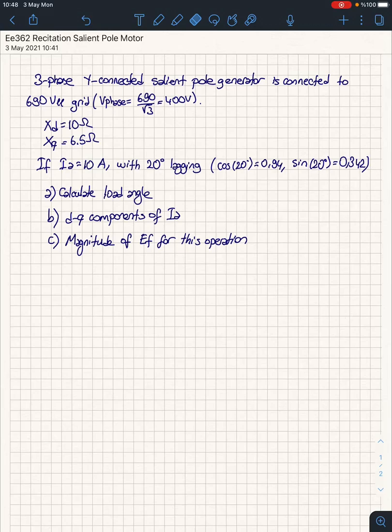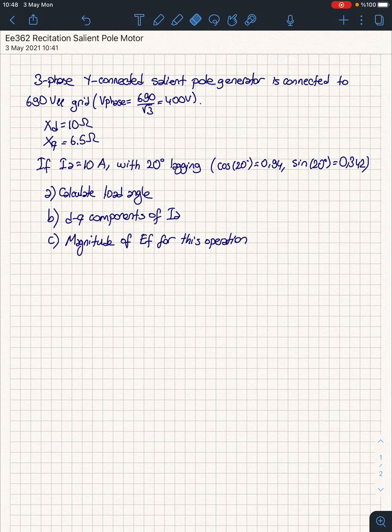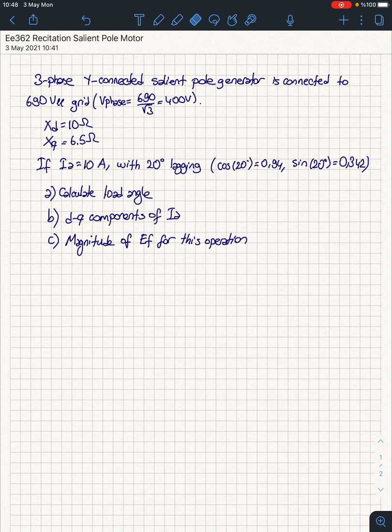Hi, today I'd like to solve a salient pole generator example. Unfortunately I left my equipment at the office, so I'll record without a camera — sorry for the sound quality. We have a three-phase Y-connected salient pole generator connected to a 690V line-to-line grid, which makes our phase voltage around 400V. Xd is 10 ohms and Xq is 6.5 ohms. The armature current is 10 amps at 20 degrees lagging. We have cos(20°) and sin(20°) tabulated.